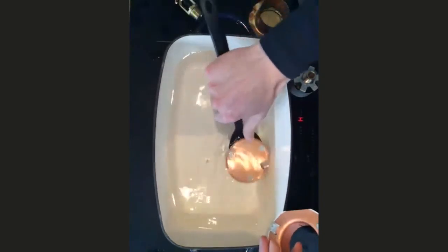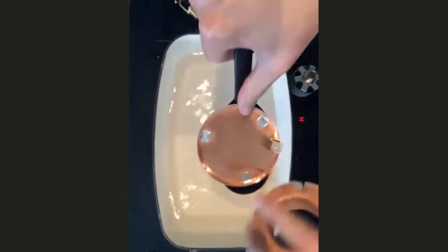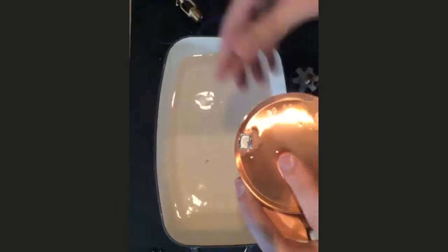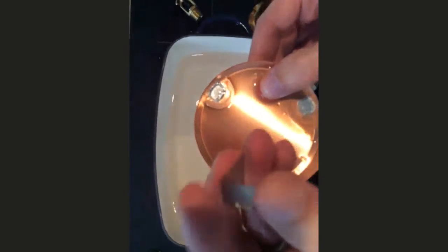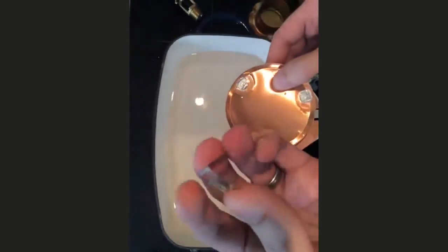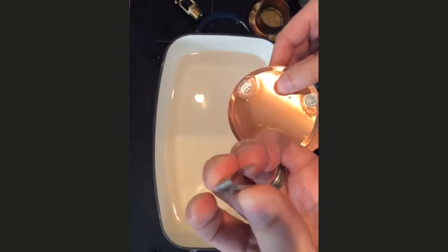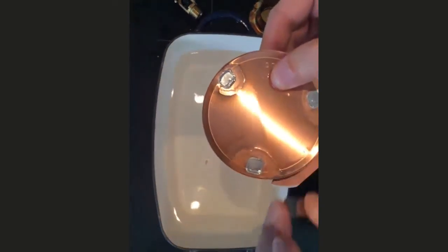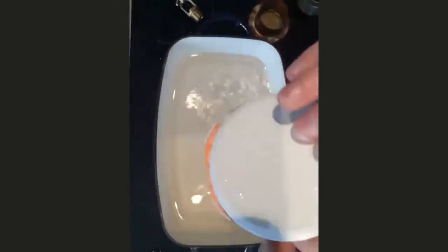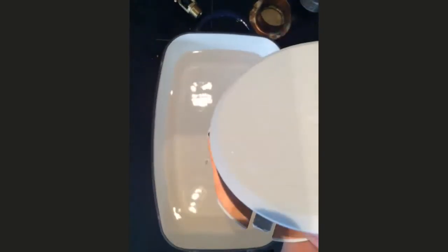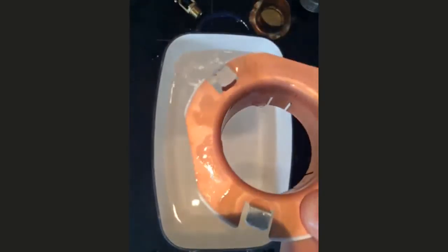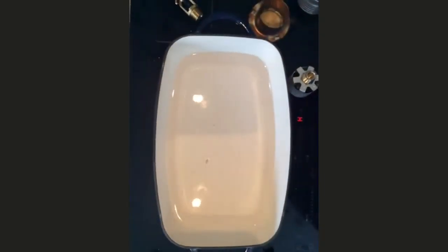Slightly different design to the one I showed you previously. So this has got two main pieces, and then this little bit, the folded metal here, which again is just designed to give it a little bit of spring, just to force the two apart. So when the solder joint is broken, it just makes it go ping, rather than slipping and sliding and moving and wondering about whether it's going to come off or not. And obviously that's what you want. You want that to come away well in advance of the head operating.